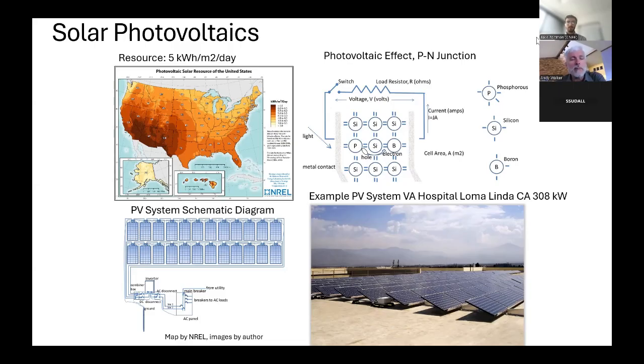Little schematic diagram to show each one of those PN junctions produces about 0.6 volts. If I put 100 of them in series, I would have a 60 volt module. If I put 10 of those in series, I would have a 600 volt string. And 600 volt is the limit for rooftop applications, residential and commercial. But in a utility scale plant, you could go up to 1500 volts DC, and products are being developed for 2000 volts DC. And then that's DC, so an inverter converts that into alternating current compatible with the voltage and configuration of phases on the utility side.